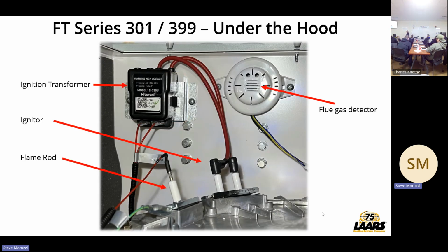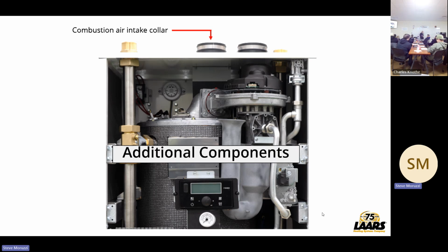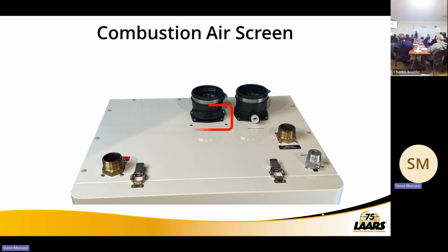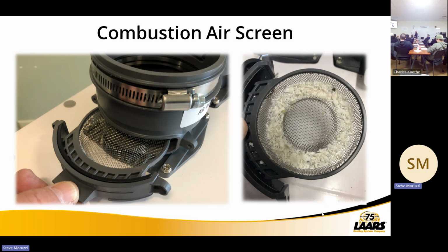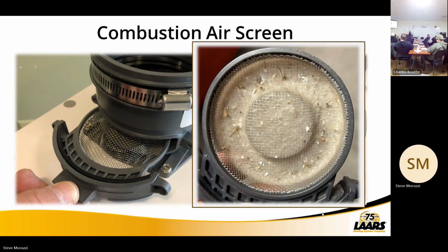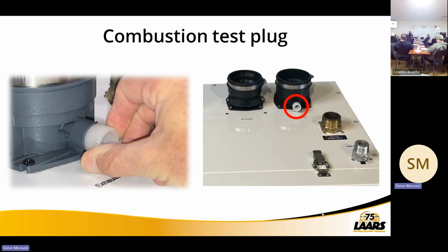Other additional components here, your ignition transformer. We saw that on one of the other videos of how to troubleshoot that. You have your igniter, your flame rod, and there is that CO2 flue gas detector. So if flue gases are entering that cabinet, it will identify that and display that right on your display, unless you choose that as a hard lockout. Combustion air in and exhaust out. And again, we have that screen or strainer to protect that burner. And you've got your exhaust collar right here.